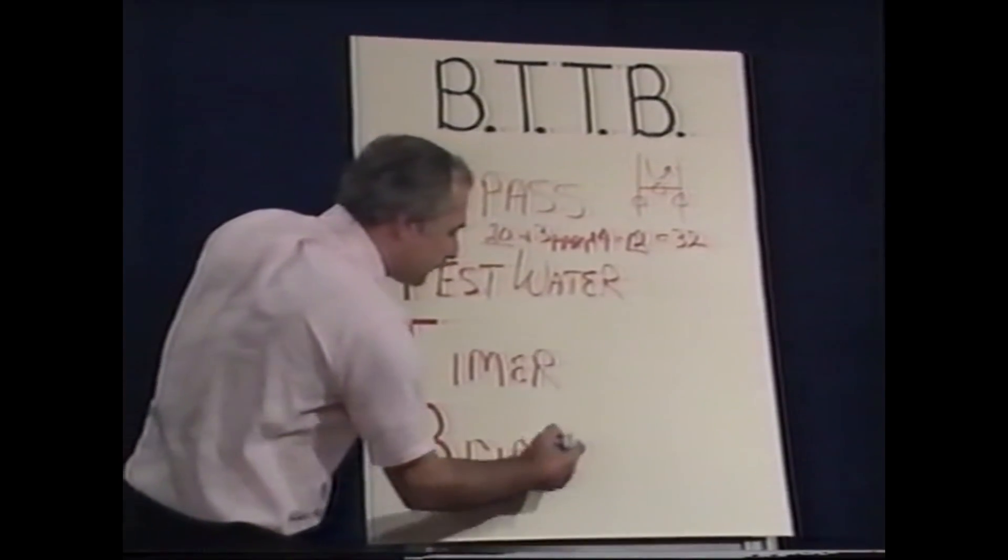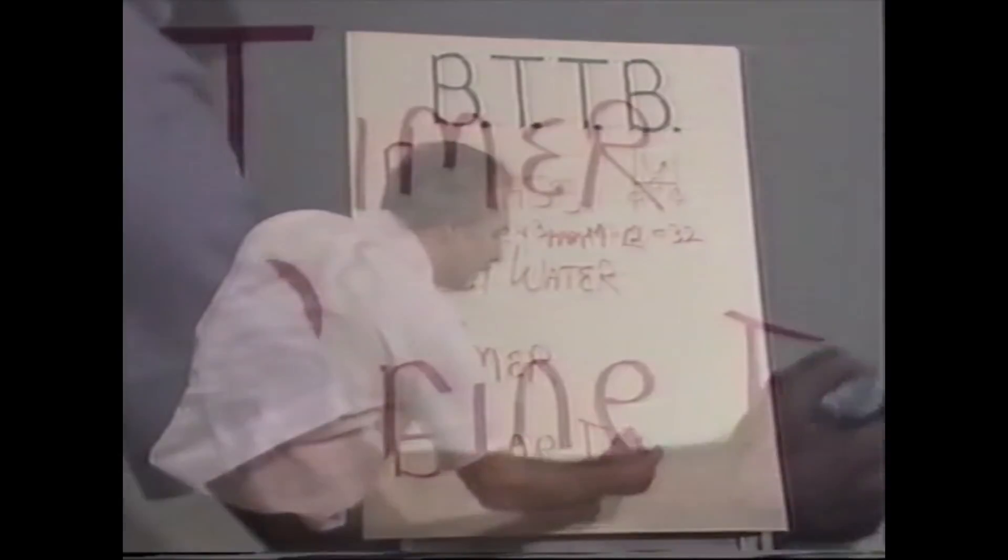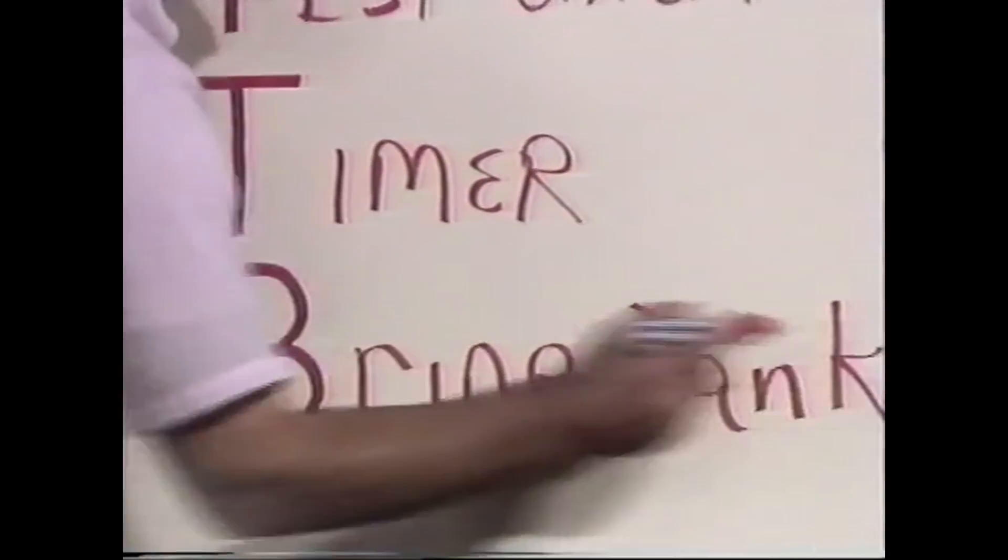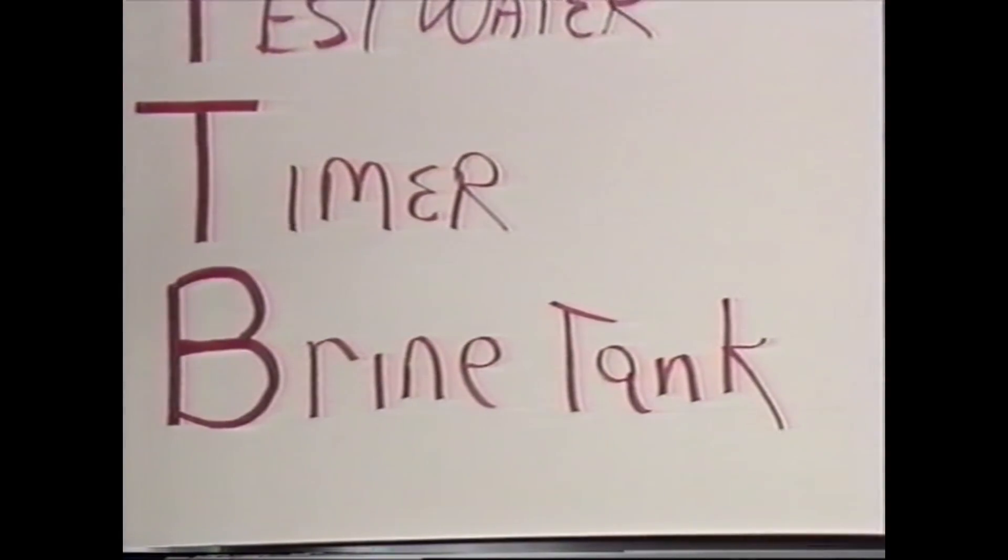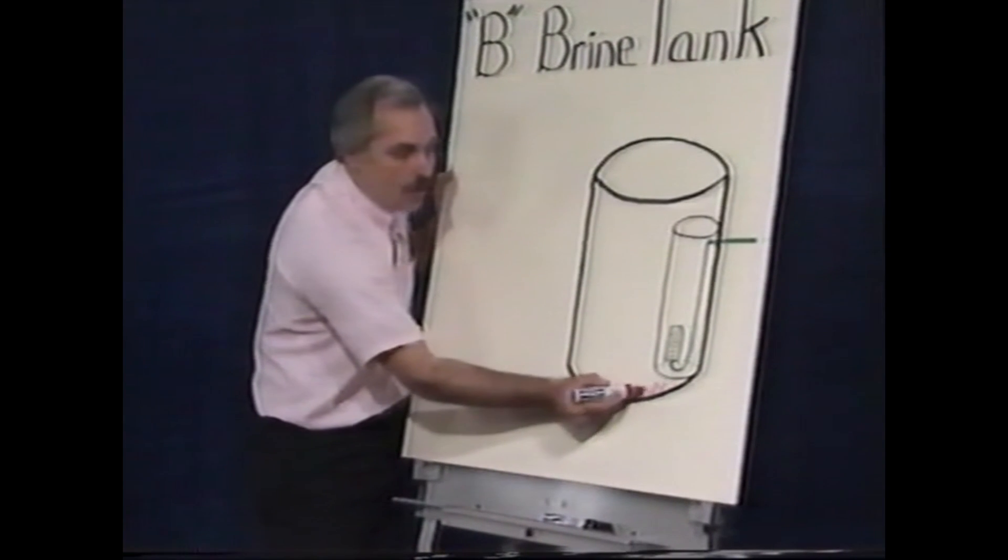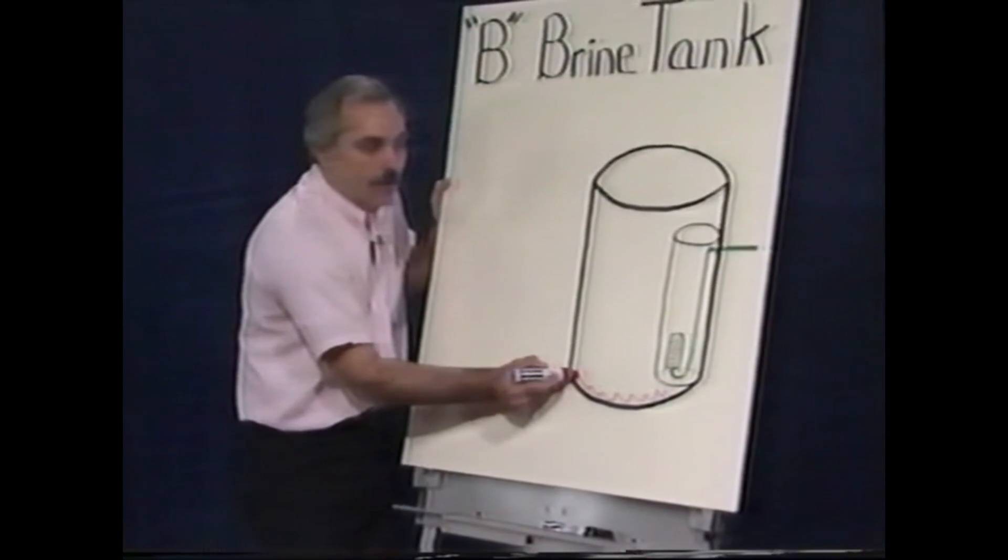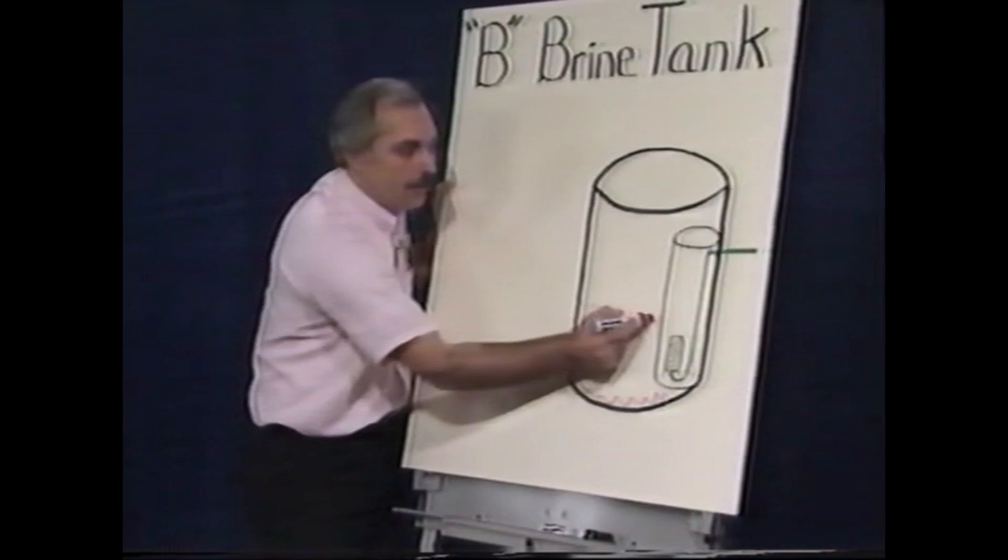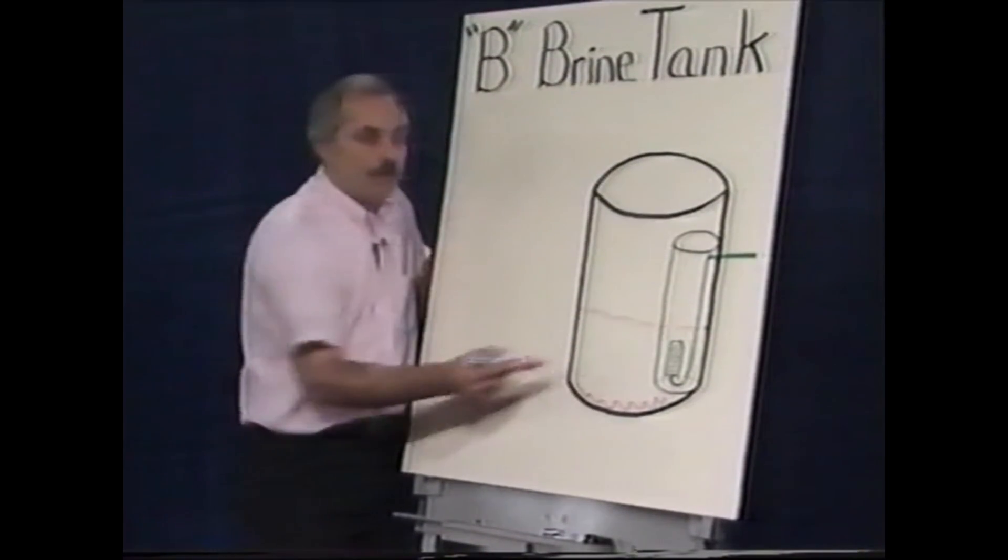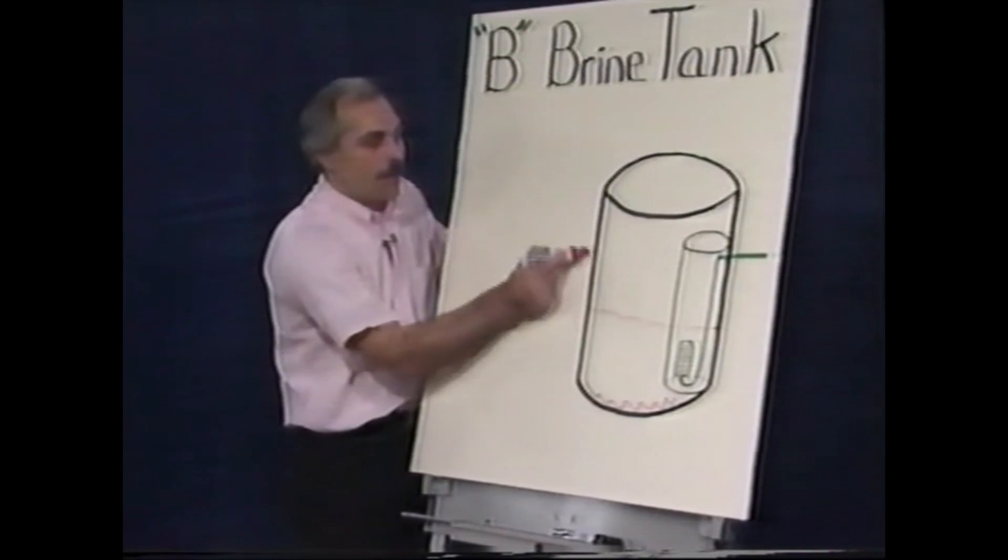When checking the brine tank for the obvious - having salt - many times people will pull the lid off the top of the tank and see a dusting of salt down at the bottom. The water level is up here, and if you siphon water right off the top, you might end up with a 30 to 40 percent concentration.